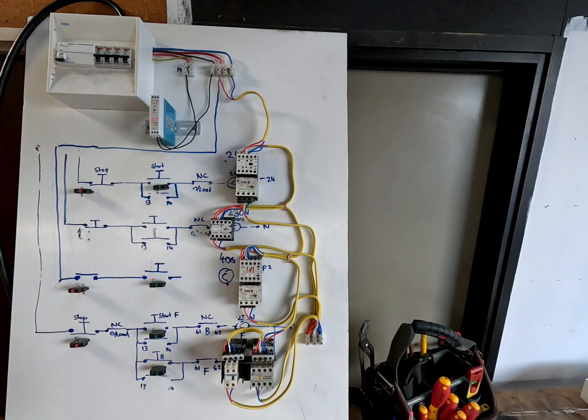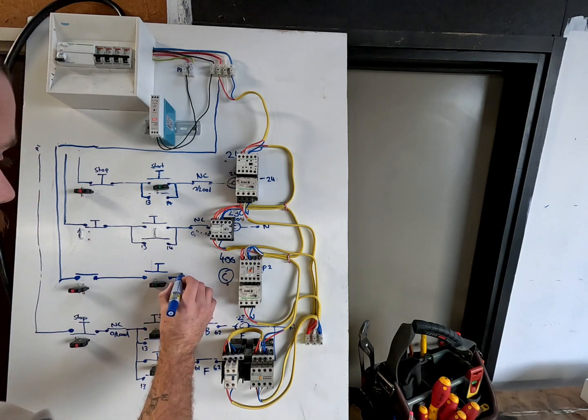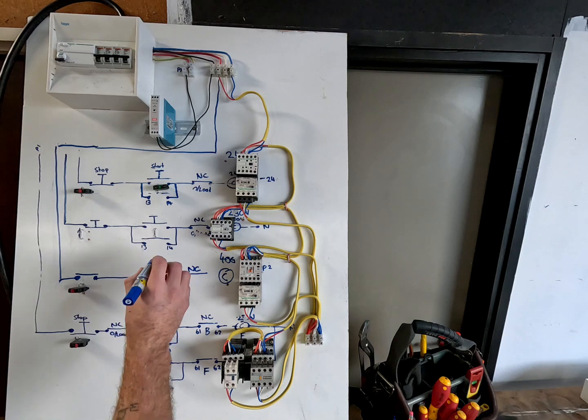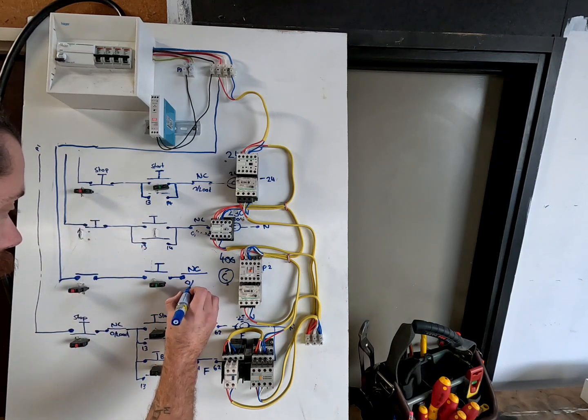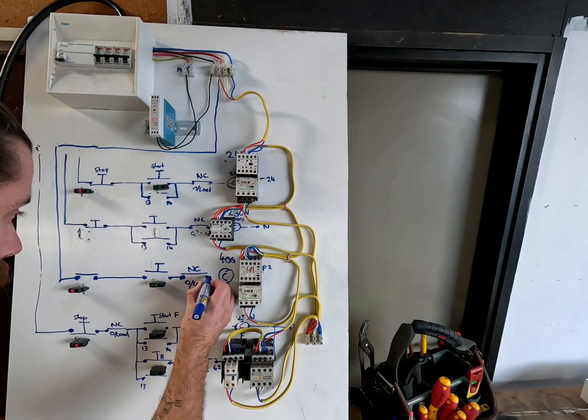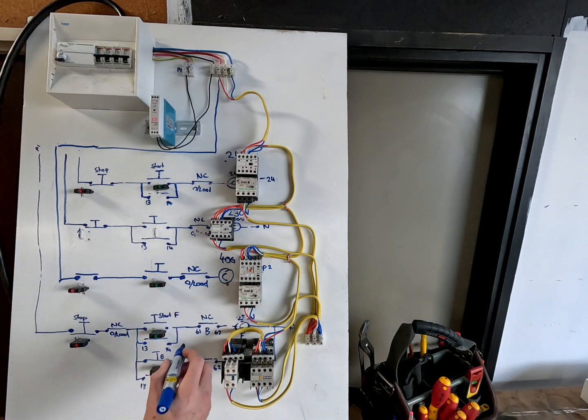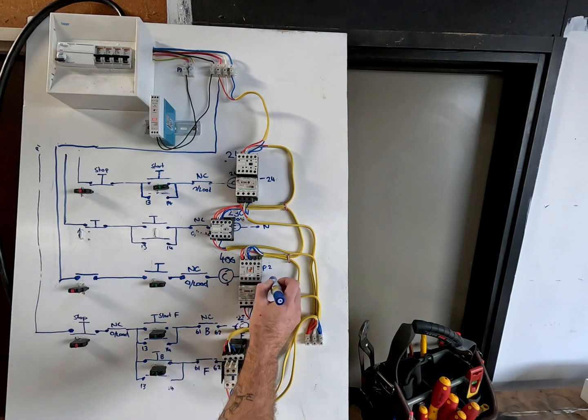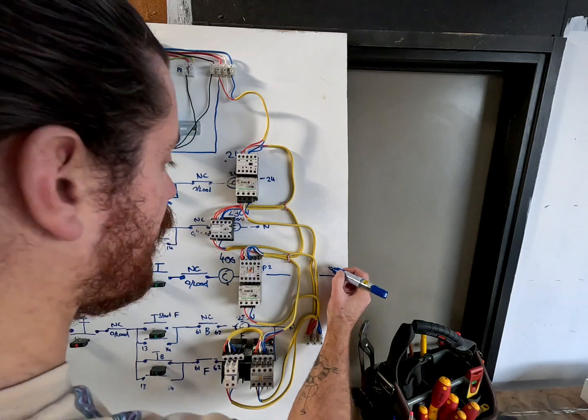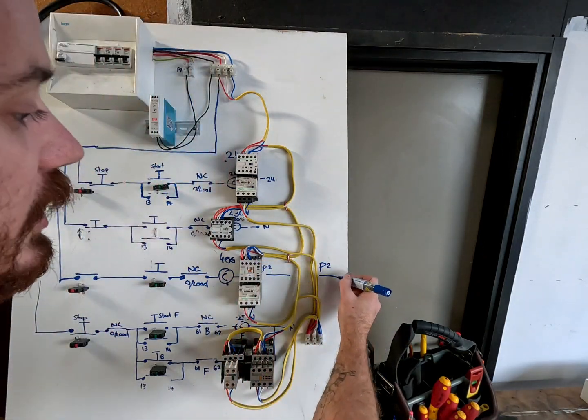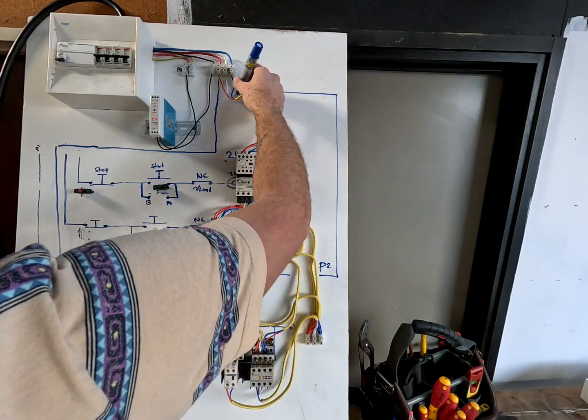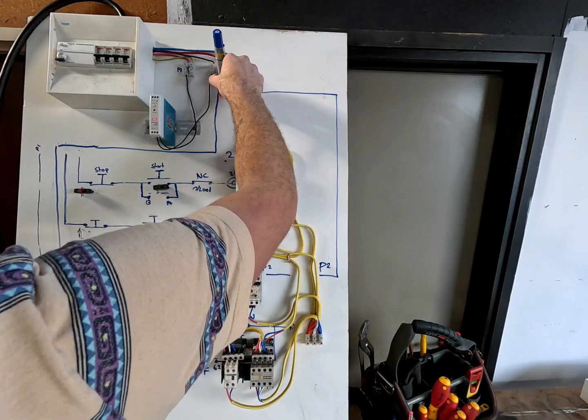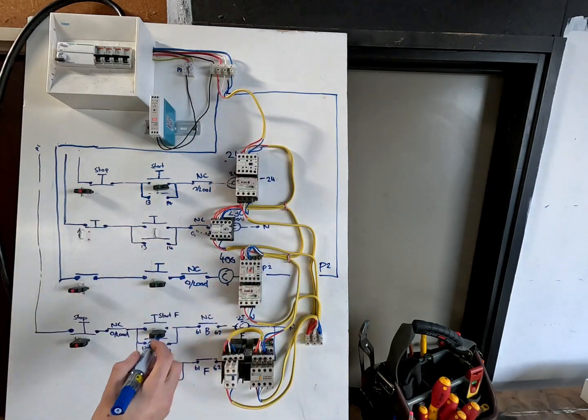Then it goes through the normally closed of the overload. Remember, an overload is also a stop button. Then onto the coil, out of the other end of the coil. We'll bring it out this side, goes to phase two or whatever other phase you didn't use on the first one. So it could go to two or it could go to three. We'll bring it along and we'll put it into two.